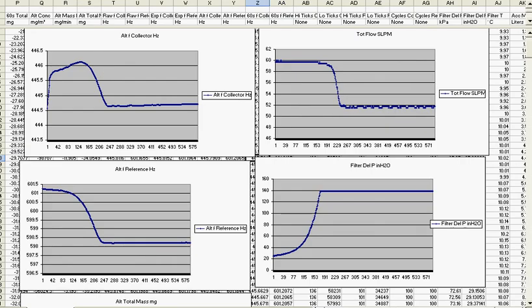This is a bad sensor. It's known as 0303. And what we show here is the alt collector. The collector resonant frequency goes up instead of going down. So what's happening here is with the smallest amount of collection of particulate, the filter's getting closer and closer to the filter holder, showing that the mass is decreasing because the lever arm is decreasing. And then at this point here, the filter starts to seat fully, and we have a monotonic increase in mass.